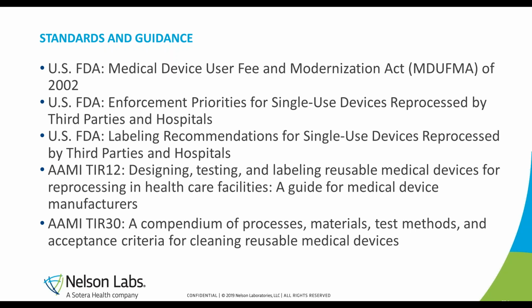Additional guidance documents and standards apply to third-party reprocessing firms as well. The FDA recommends using guidance from the Medical Device User Fee and Modernization Act of 2002, commonly referred to as MDUFMA, along with enforcement priorities for single-use device reprocessing by third parties and hospitals. Because a single-use device is manufactured by an original manufacturer but typically reprocessed by a third party, additional labeling requirements are instilled. These requirements are found in labeling recommendations for single-use devices reprocessed by third parties and hospitals.